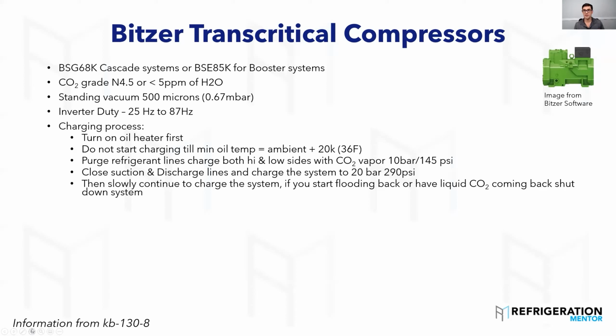Purge refrigerant lines through high and low side. So actually no different than your standard refrigerant, getting that CO2 vapor and purging those lines so you're not getting anything into the compressor.